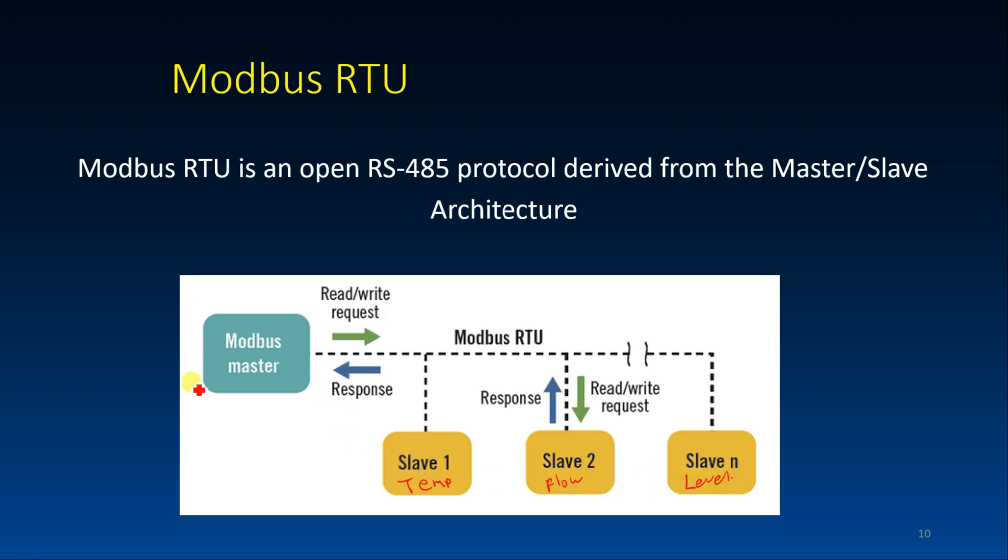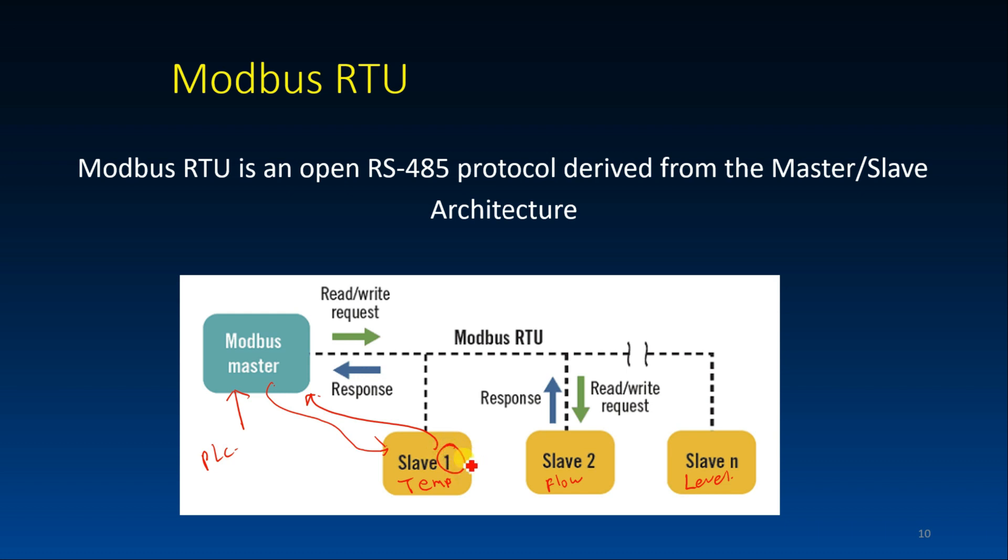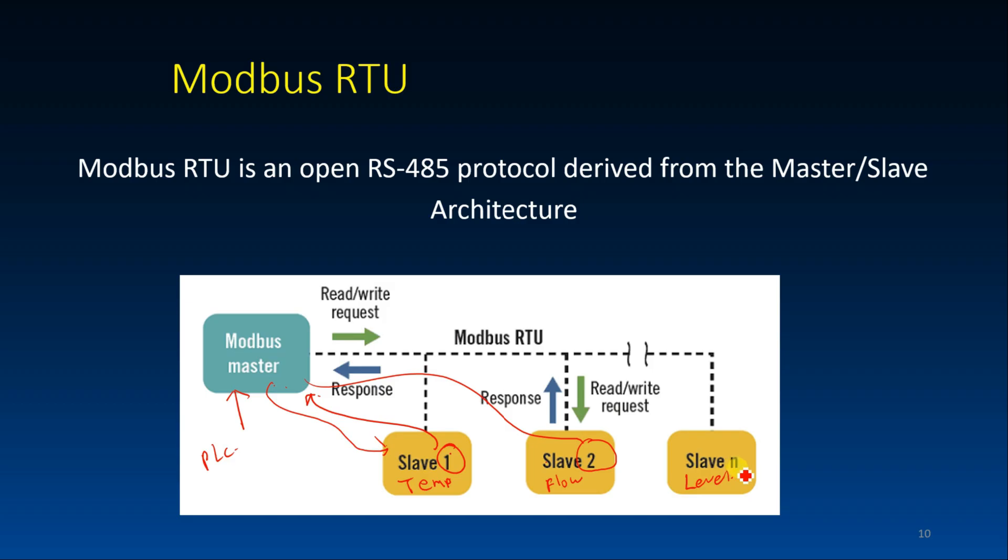So let's say the master, this one can be a PLC. The master will ask slave 1 what is the temperature. So the slave will reply. And one thing is that only the master can send a request. So the master will request each slave data at a time using these addresses. If it wants to address slave 1, it just addresses slave 1. And this goes like this. So it can address flow sensor too, and also this one which will be slave.